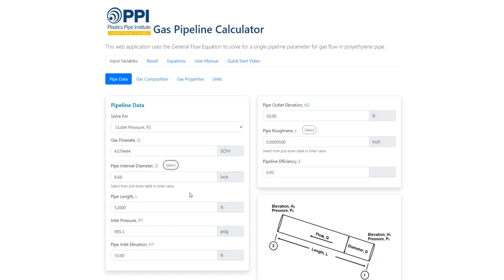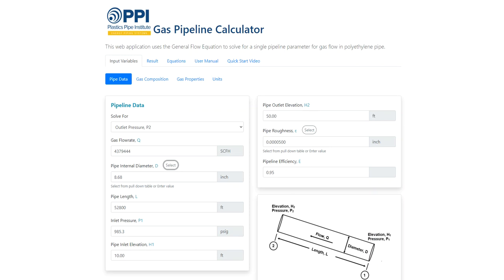If the internal diameter changes along the length of the pipeline to be modeled, the user's manual describes a method to estimate the equivalent pipe length for a given ID. The elevation of the pipe ends can be entered as H1 and H2. The highest and lowest points along the pipeline can be used instead of the actual inlet and outlet elevations. The difference in elevation used in the calculator generally has little effect on the results. The pipe roughness is set for polyethylene; if the user would like to model a different pipe material, the roughness value needs to be manually changed.